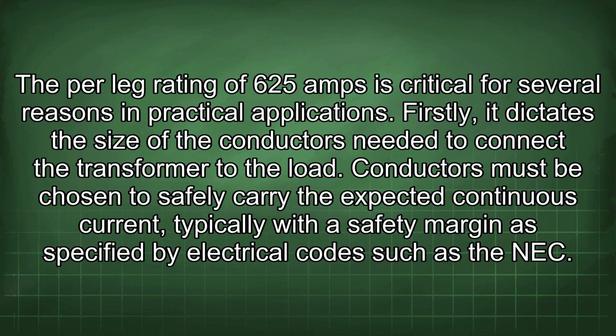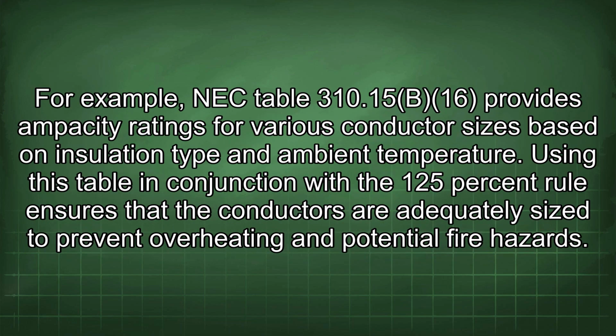Firstly, it dictates the size of the conductors needed to connect the transformer to the load. Conductors must be chosen to safely carry the expected continuous current, typically with a safety margin as specified by electrical codes such as the NEC. For example, NEC Table 310.15(B)(16) provides ampacity ratings for various conductor sizes based on insulation type and ambient temperature. Using this table in conjunction with the 125% rule ensures that the conductors are adequately sized to prevent overheating and potential fire hazard.